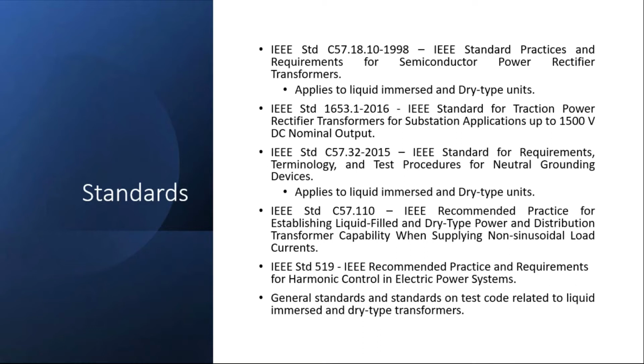1653.1, and this is covering mostly the traction power rectifier transformers up to 1500 volt. This transformer has the usual service conditions and the design requirement, and this details the loading requirement for the traction application. So we have light, medium, and heavy duty requirement. And the next one is C57.32. This is mainly for grounding transformers.